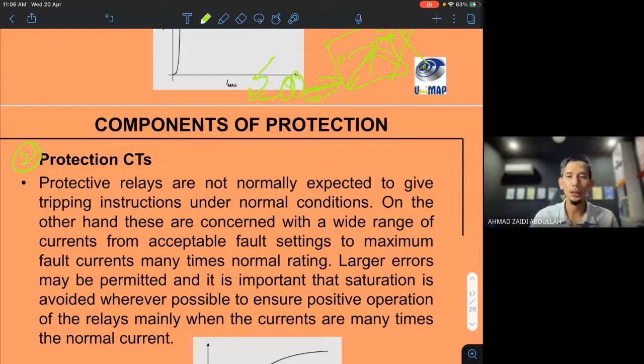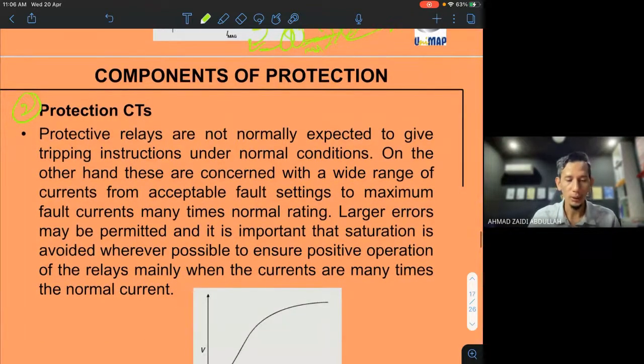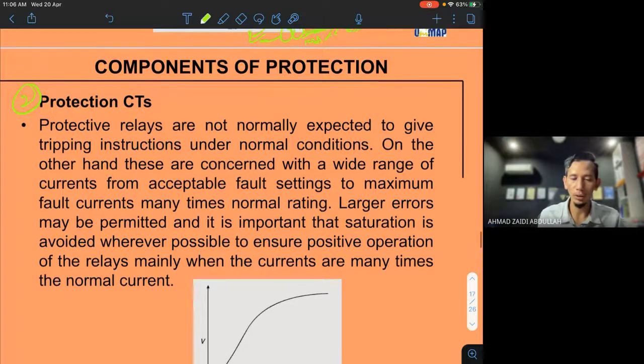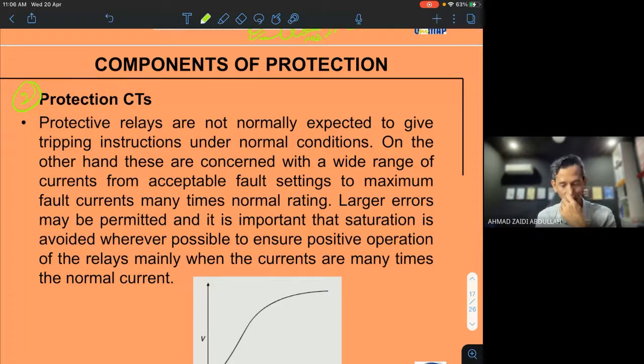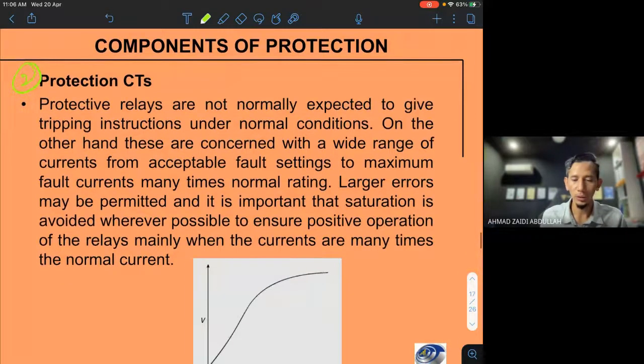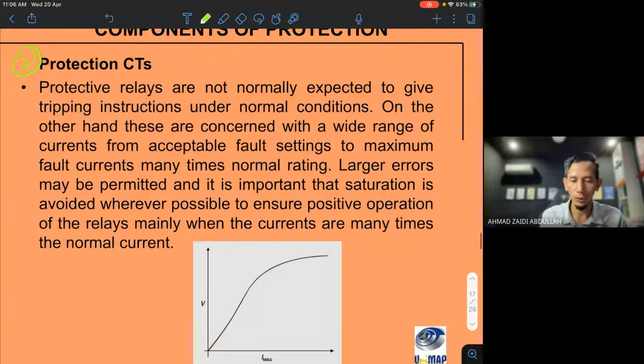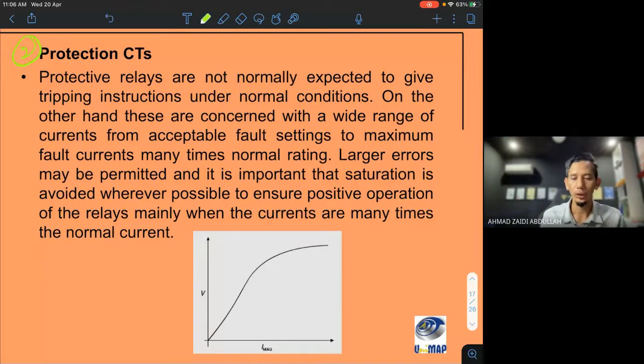And then the second thing is protection CT. So for protection CT, protective relays are not normally expected to give tripping instruction under normal condition. On the other hand, there is a concern with a wide range of current from acceptable fault setting to maximum fault. So that's why we need protection CT. Its curve looks like this, not the same as the magnetizing curve. So the concept is the same as before.